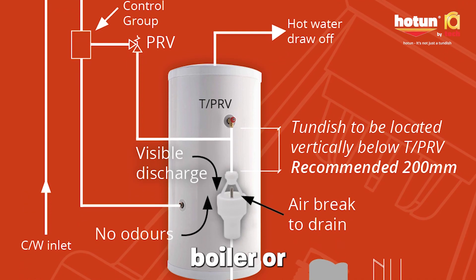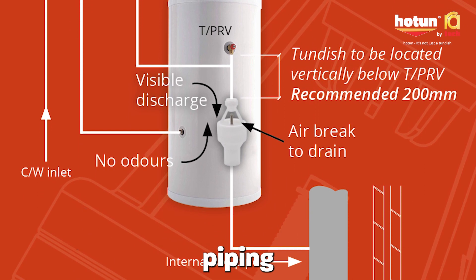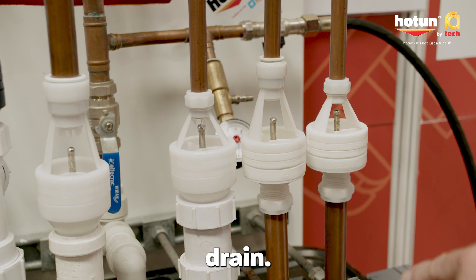On an unvented cylinder you've got a TPRV — you would normally run that to outside, but if you've got a landlocked boiler or a landlocked cylinder, you've then got the issue of taking up floors, running piping through joists, all that stuff which is difficult to do, takes a lot of time and a lot of cost. You can use the Hotun tundish and it allows you to then run out into an internal drain.